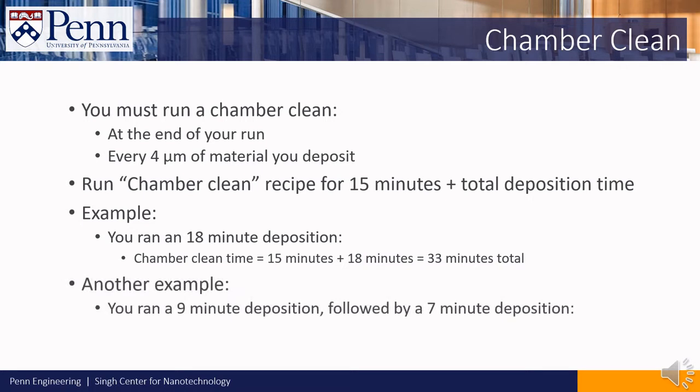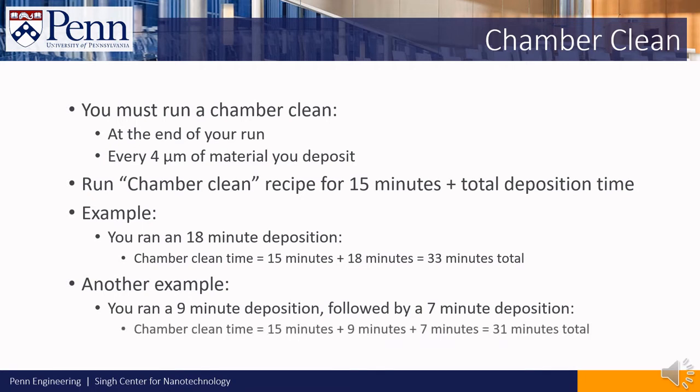As another example, suppose you ran a 9 minute deposition on one sample and a 7 minute deposition on your next sample. You should run the chamber clean for 15 plus 9 plus 7 minutes for a total of 31 minutes.